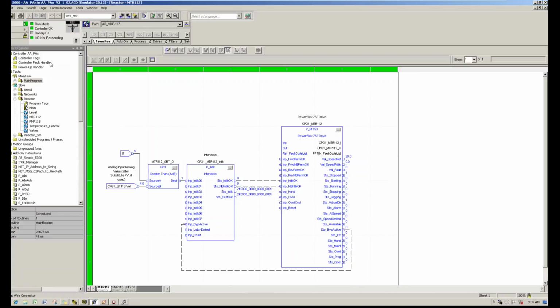Now the way this tool works is that we associate it with a logic controller, which I've already done here. So this reference here, AA_PAX, is the name of my Logix controller. You'll see here up in the top left-hand corner where it says RSLogix 5000 AA_PAX. That is the name of my program. So I've linked the Alarm Builder tool to that Logix program, and then I've also associated it with my HMI application. Right, so that's a couple of little setup things that take a few minutes to do.